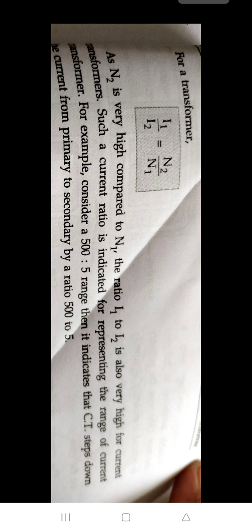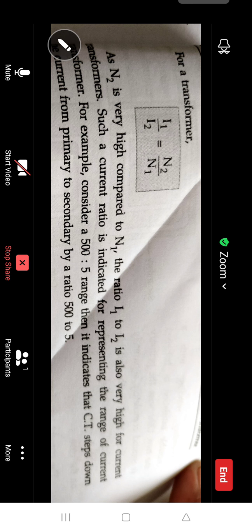It means whenever the line carrying conductor has 500 ampere on the primary, the secondary will be 5 ampere. We can also say vice versa, that whenever we measure 5 ampere on a meter, the line carrying current on the primary side is around 500 ampere. According to this we can measure how much primary current is going in the conductor.